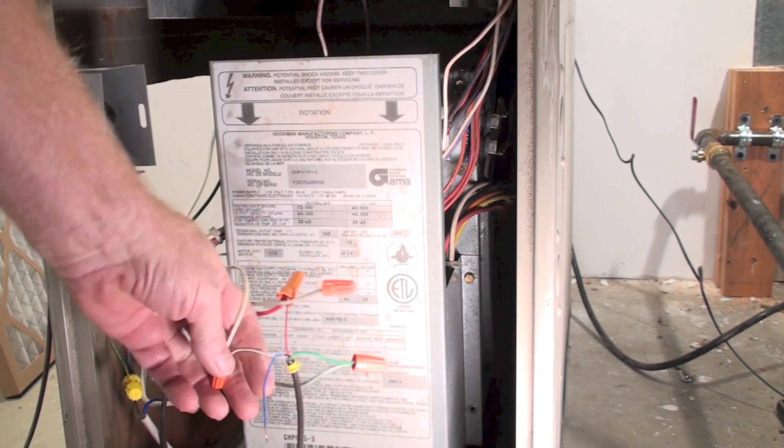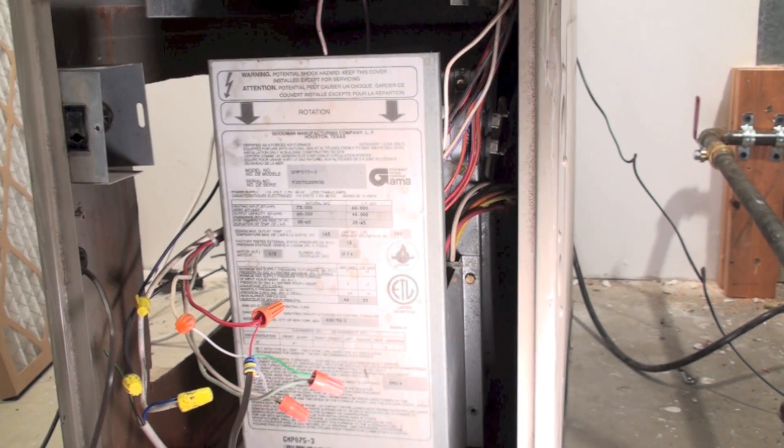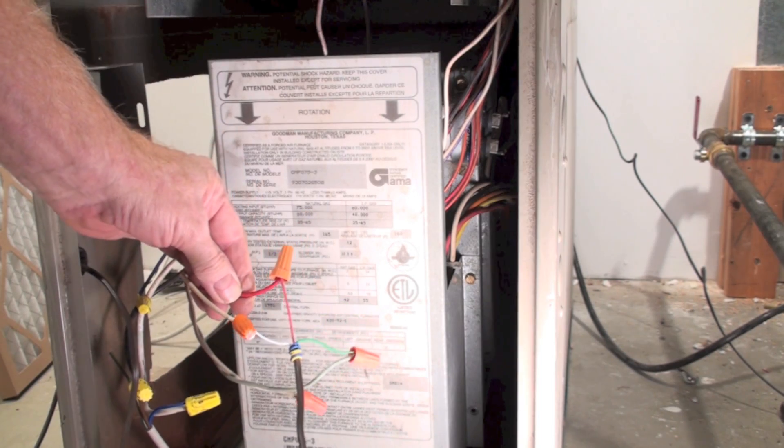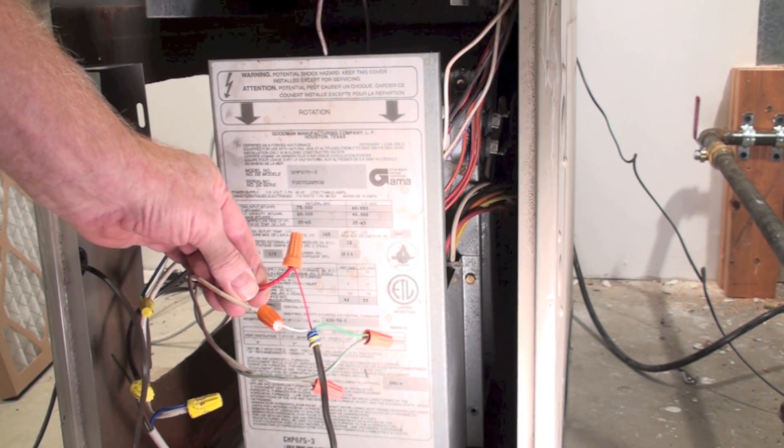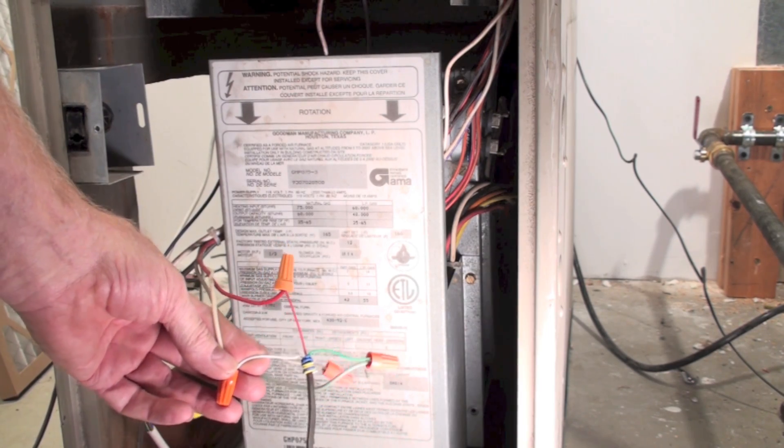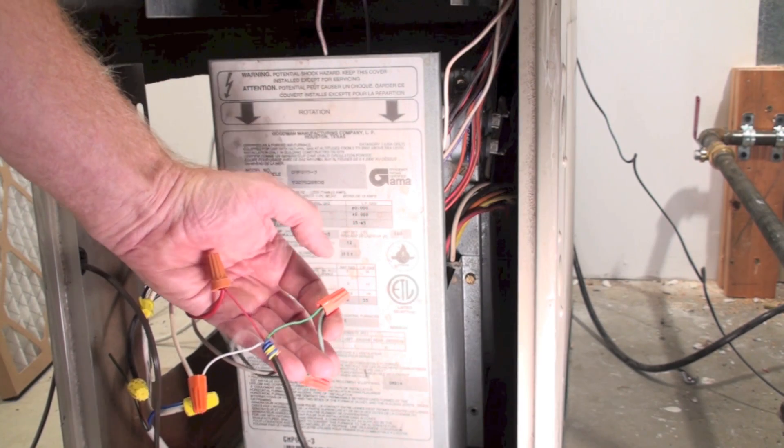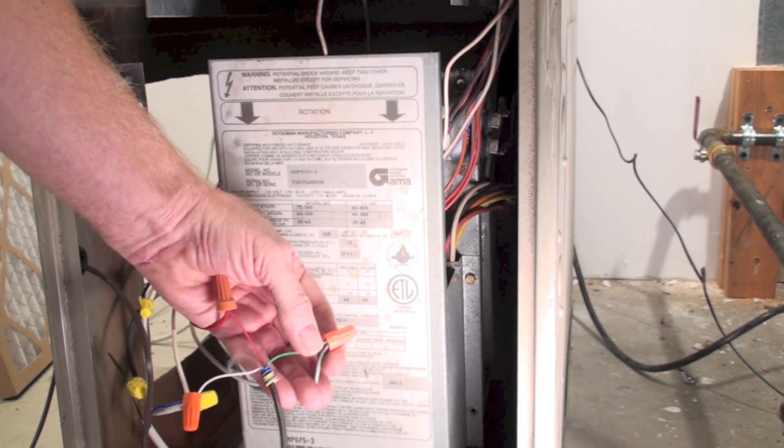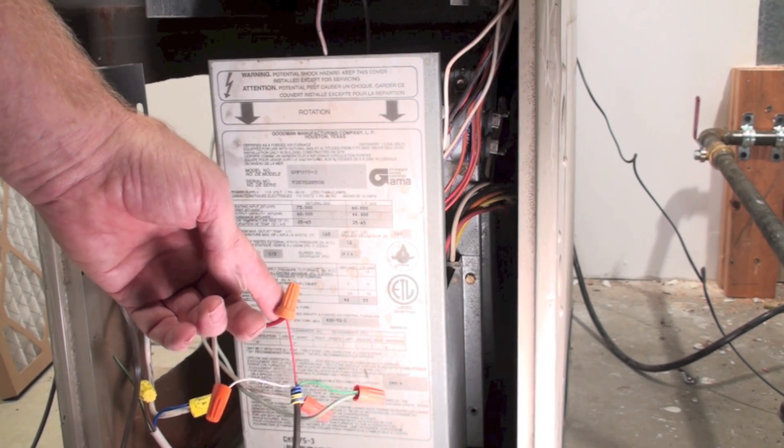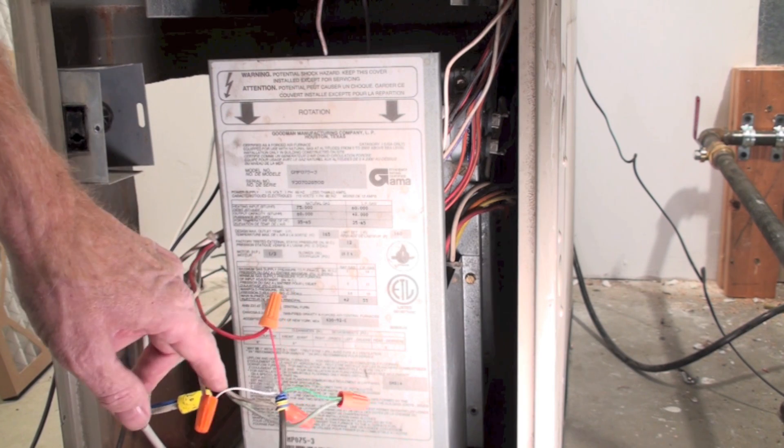So, what I've got hooked up here, we've got red coming out of the control going up to the thermostat, white coming out of the control going up to the thermostat, and green coming out of the control going up the thermostat. Red is a power source. That's a low voltage power that is fed up to the thermostat. It goes up to the thermostat through red and comes back through white.